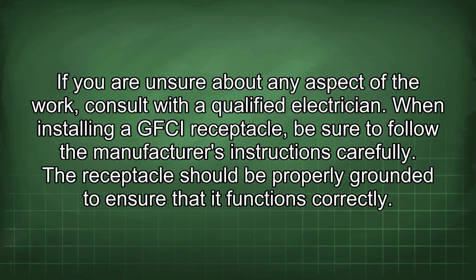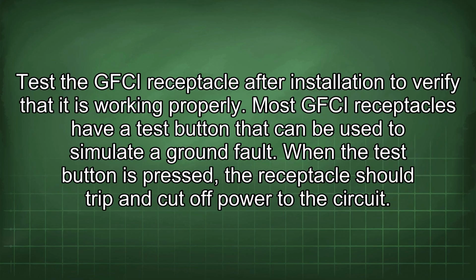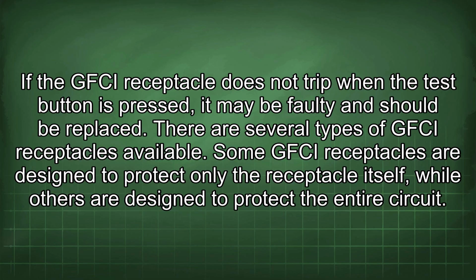When installing a GFCI receptacle, be sure to follow the manufacturer's instructions carefully. The receptacle should be properly grounded to ensure that it functions correctly. Test the GFCI receptacle after installation to verify that it is working properly. Most GFCI receptacles have a test button that can be used to simulate a ground fault. When the test button is pressed, the receptacle should trip and cut off power to the circuit. If the GFCI receptacle does not trip when the test button is pressed, it may be faulty and should be replaced. There are several types of GFCI receptacles available.